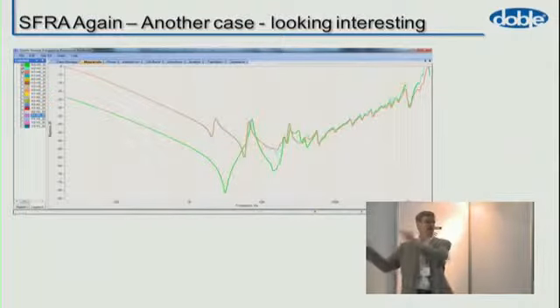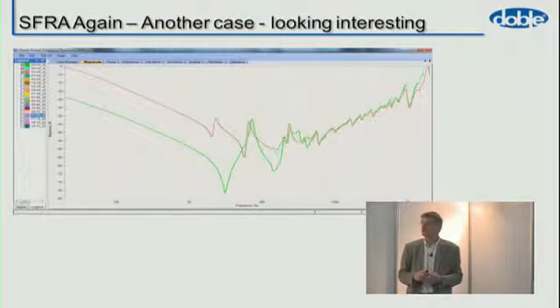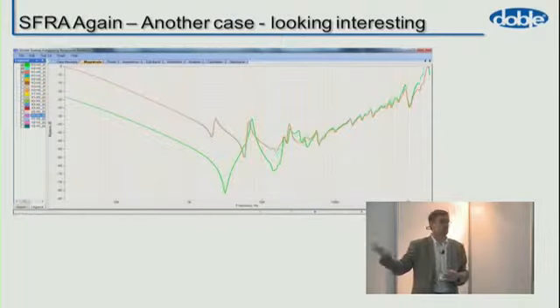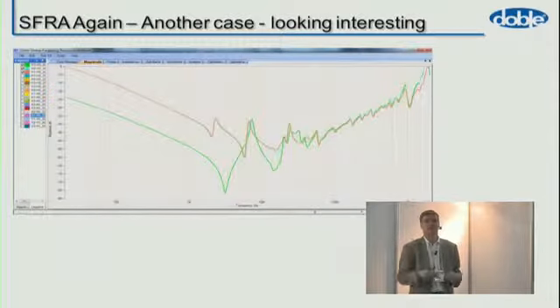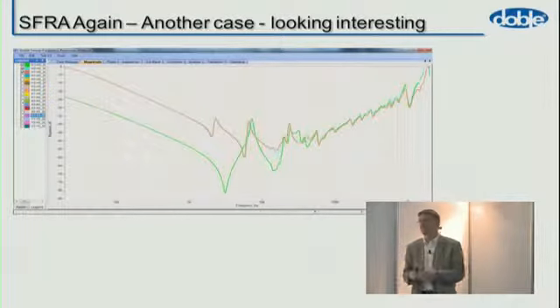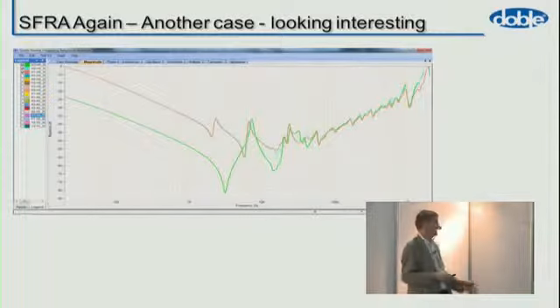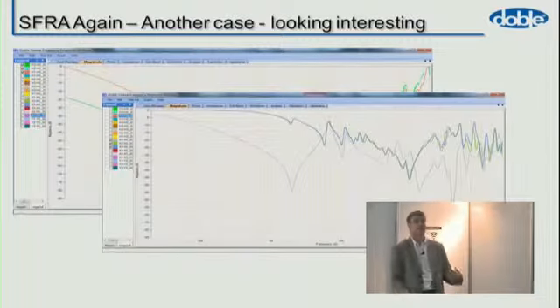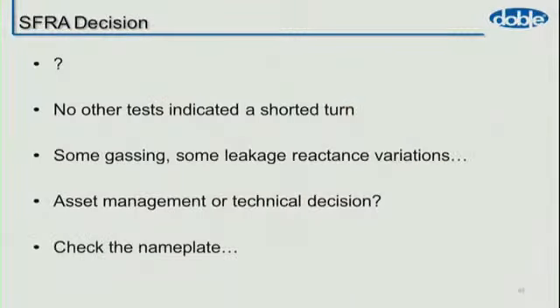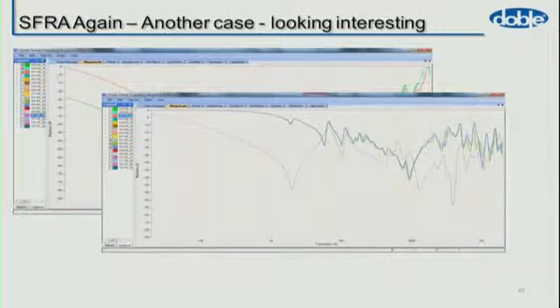It's not often I get people invading the stage, but Peter's allowed. This transformer was taken out of service. Golden rule, if you took it out, it goes back in. There has to be a really good reason if you have taken a transformer out of service that it doesn't go back in. In this case, there's a lot of variation between the phases. But what you have to do is say the data in the SFRA here tells me there's a shorted turn on that transformer.